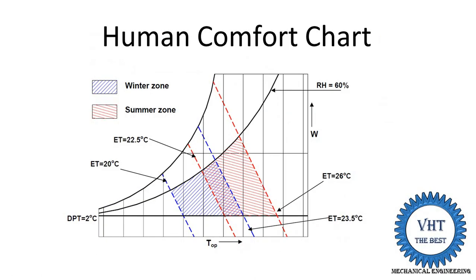In this chart they changed three parameters: temperature, relative humidity, and air motion. Combining all these factors gives what is known as effective temperature. The air velocity is set at 5 to 8 meters per minute, and dry bulb and wet bulb temperatures are changed for certain regions, then plotted on one graph.